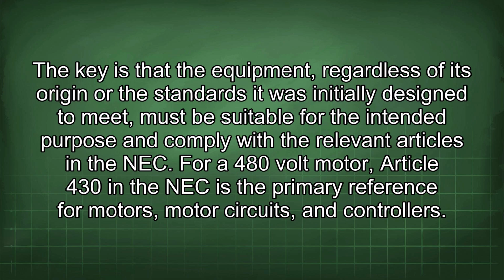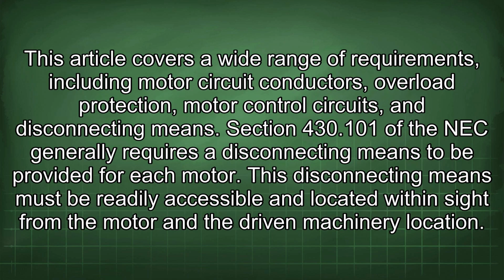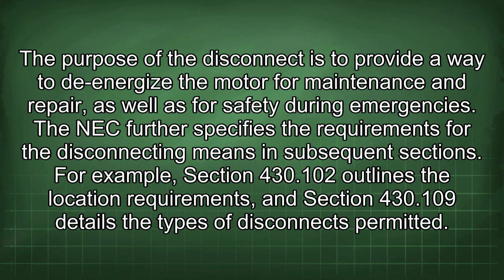For a 480-volt motor, Article 430 in the NEC is the primary reference for motors, motor circuits, and controllers. This article covers a wide range of requirements, including motor circuit conductors, overload protection, motor control circuits, and disconnecting means. Section 430.101 of the NEC generally requires a disconnecting means to be provided for each motor. This disconnecting means must be readily accessible and located within sight from the motor and the driven machinery location. The purpose of the disconnect is to provide a way to de-energize the motor for maintenance and repair, as well as for safety during emergencies.